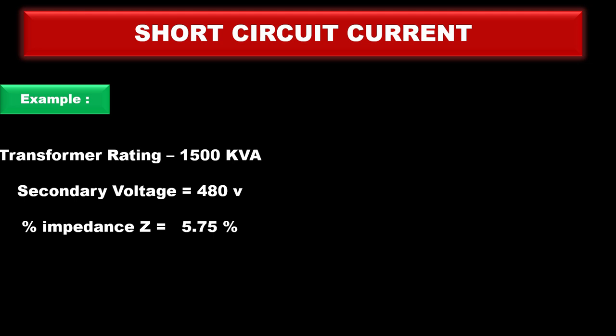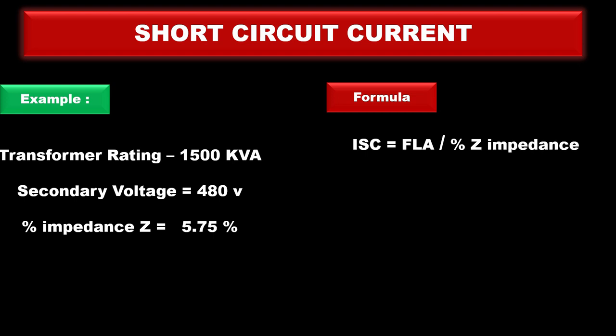Put these values in the formula. The formula of short circuit current is full load ampere divided by percent of Z impedance. Z is the symbol of impedance.